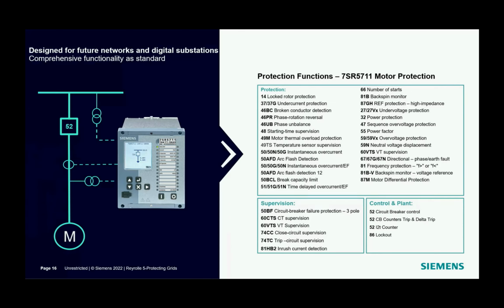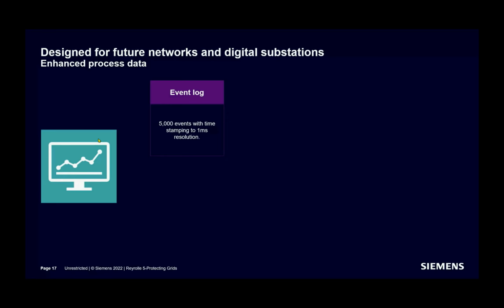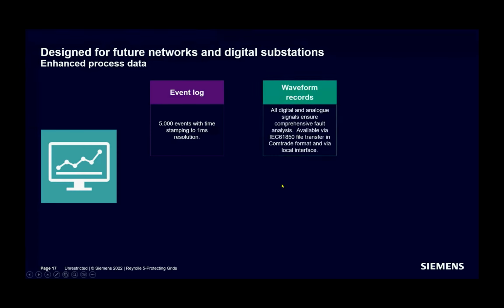Now I would like to summarize the significant points of how 7SR5 relays handle the recorded data. Now you see event log. 7SR5 relays can store 5,000 events at 1 millisecond resolution. And when it comes to waveform records, well, all analog waveform records can be accessed via local interface through the software or via IEC 61850 in COMTRADE file format. You can pull the COMTRADE file format over IEC 61850.